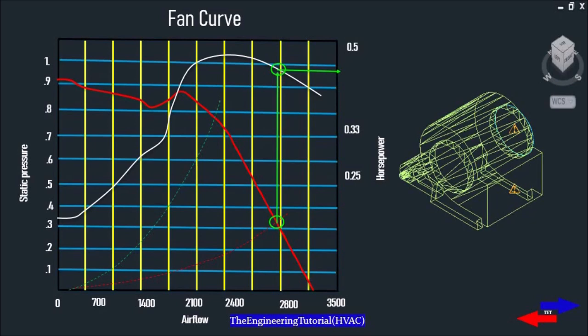is the system curve, and the green dotted line is called the surge line and it's also known as the do-not-select line. So we do not select the fan near or close to the left of that line.